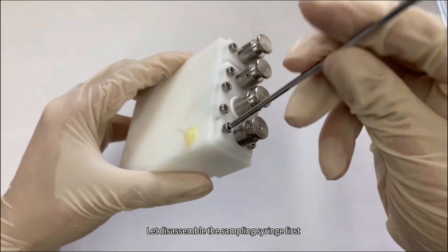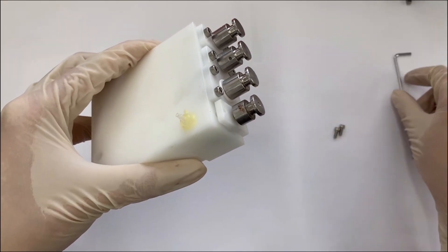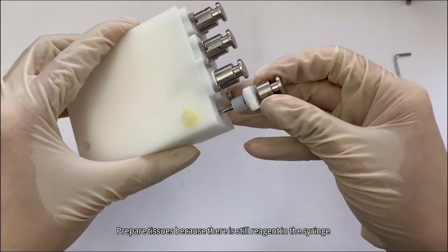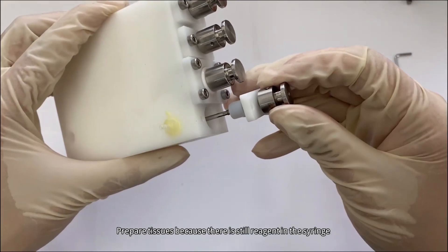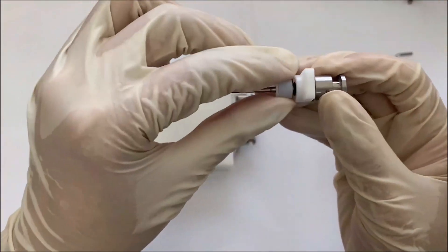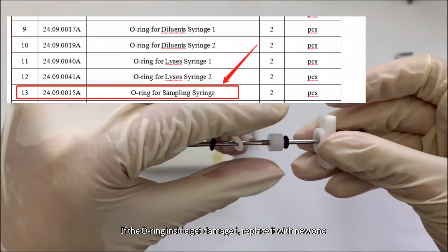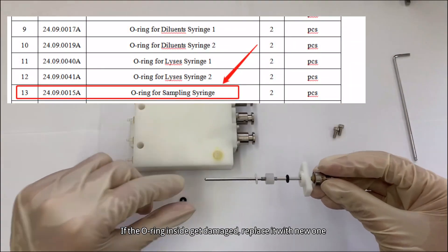Let's disassemble the sampling syringe first. Prepare tissues because there is still reagent in the syringe. If the O-ring inside gets damaged, replace it with a new one.